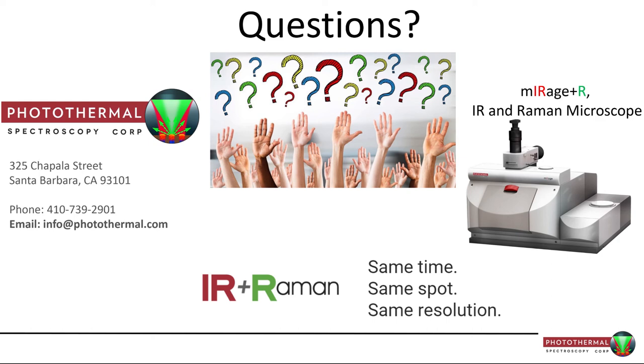Question: how do you see this new OPTIR technique complementing your Raman work or could it even replace it? Initially it will be complementary — I'm particularly excited by having the Raman add-on. Information can be complementary and the CD stretch looks a bit bigger in OPTIR. However, generating a chemical map with Raman at one wavenumber takes significant time, whereas image acquisition with the Mirage is very fast. For speed the Mirage has particular advantages; for detailed structural information you might use both.